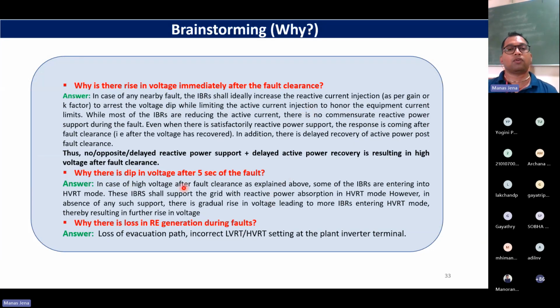In case of high voltage after fault clearance, as explained above, some IBRs are entering into the HVRT mode. These IBRs shall support the grid with reactive power absorption. Remember absorption, because you are in the HVRT. However, in the absence of any such support, there is a gradual rise in the voltage, leading to more IBRs entering the HVRT mode, thereby resulting in a further rise in the voltage. Loss of RE generation during fault, loss of evacuation path, because with high voltage many transmission lines also tripped, so you lost the evacuation path. Incorrect LVRT and HVRT settings, or the responses that we are getting from the plants, is what caused the trippings.